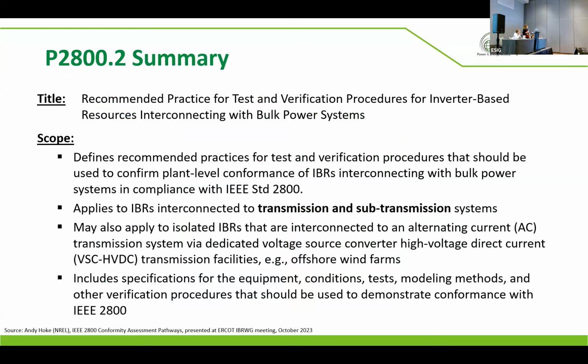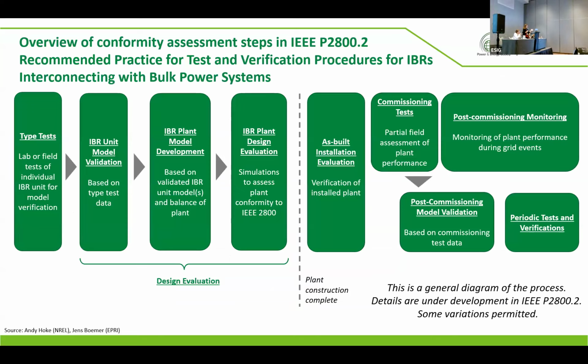So I mentioned 2800.2. Just to repeat again, basically that's a recommended practice to test and verify if inverter-based resources interconnecting to the bulk power system are indeed 2800 compatible. Currently, there are subgroups within this 2800.2 development process working on various pieces of verification. And this is split into type tests. So this is basically where single inverters will be tested at manufacturer facilities to make sure that the inverter itself has some capabilities that are compatible with 2800 requirements.